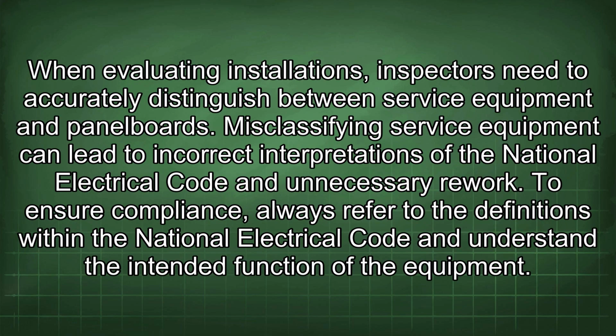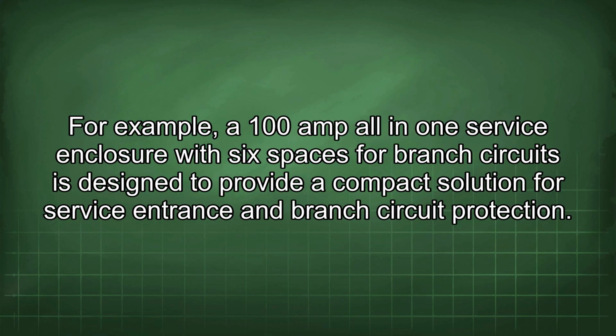When evaluating installations, inspectors need to accurately distinguish between service equipment and panel boards. Misclassifying service equipment can lead to incorrect interpretations of the National Electrical Code and unnecessary rework. To ensure compliance, always refer to the definitions within the National Electrical Code and understand the intended function of the equipment. For example, a 100 amp all-in-one service enclosure with 6 spaces for branch circuits is designed to provide a compact solution for service entrance and branch circuit protection.